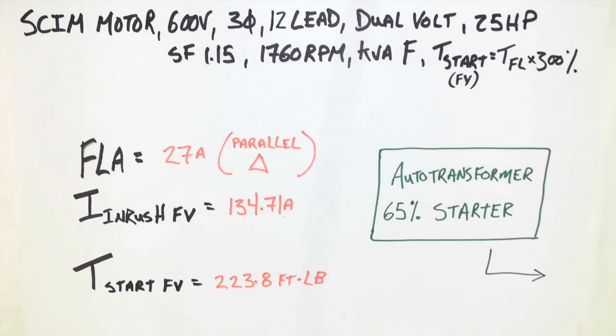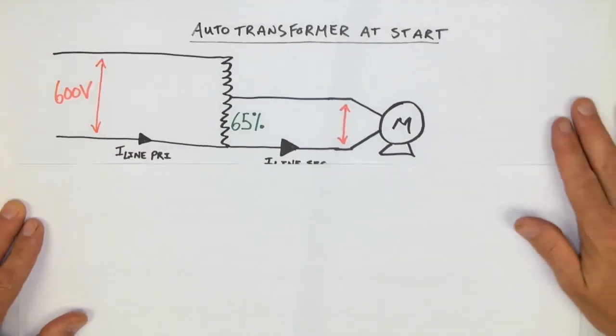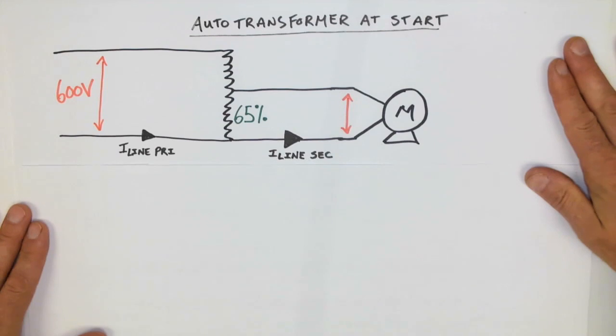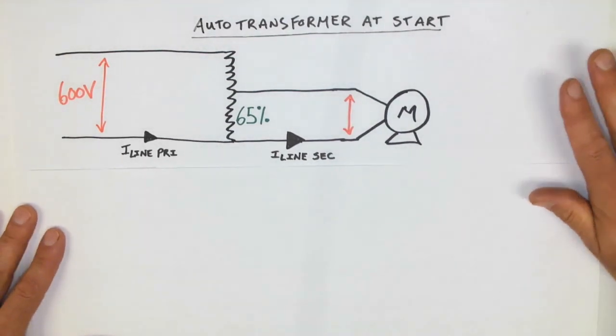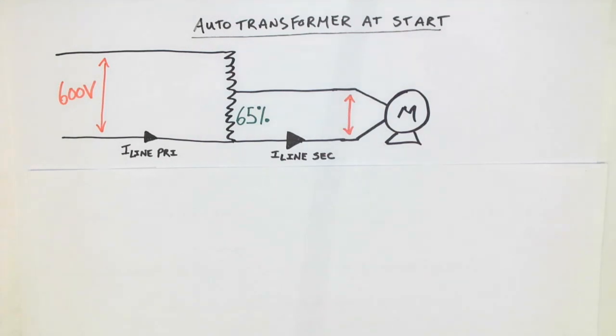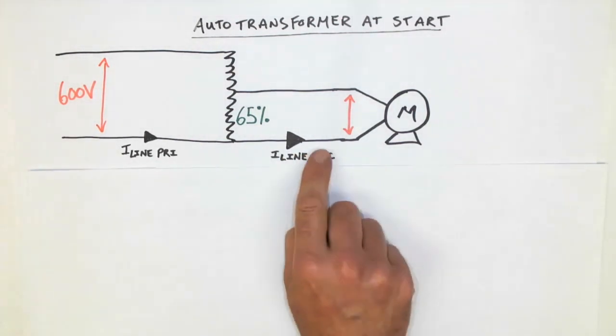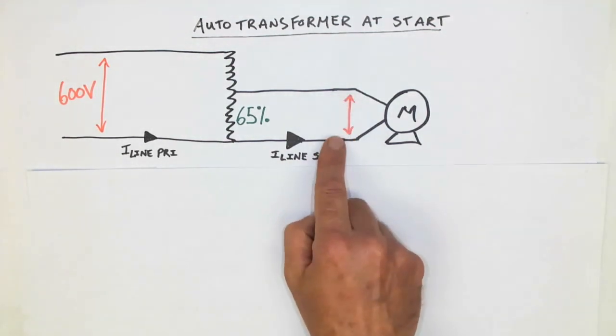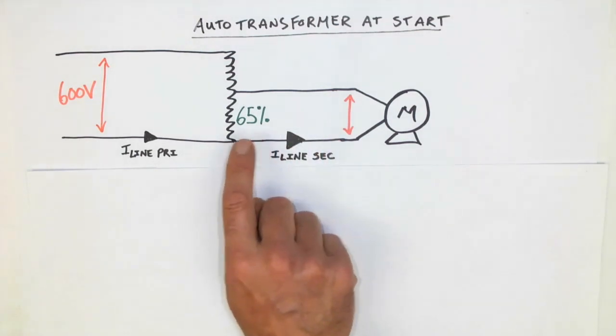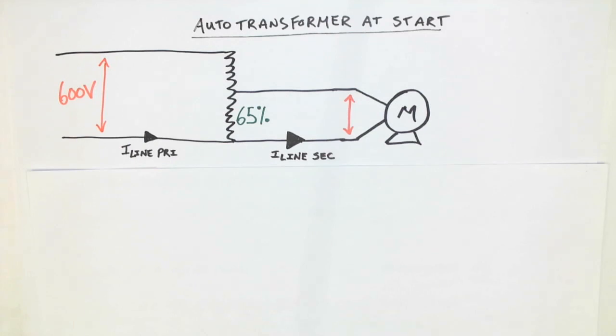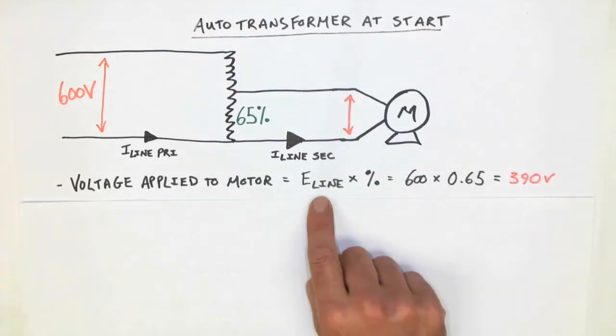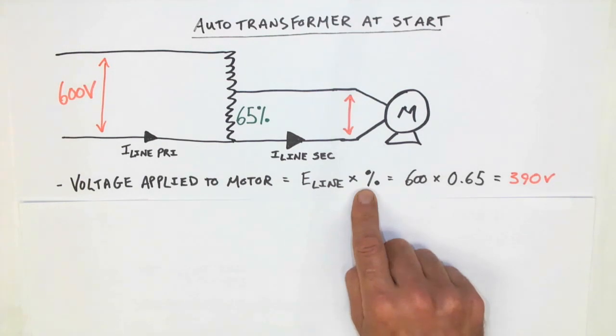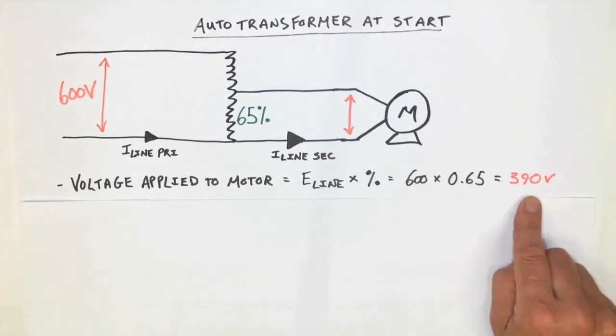So let's take a look at this autotransformer at start and see if we can work out some of the current values. Here's a simplified diagram of an autotransformer at start. I've only included a single line in there to clarify and simplify the process. We have 600 volts coming in on the line side, and on the load side, we have a 65% tap, meaning that the line voltage should be 65% of the initial 600 volts. E line times percent, so 600 times 0.65 should give us 390 volts.